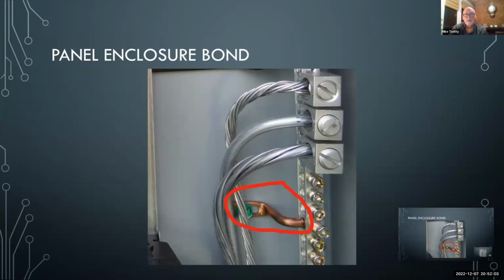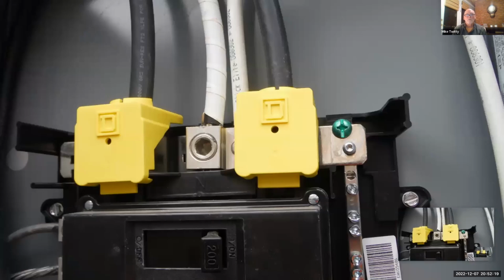That's probably aluminum, and that's probably a water pipe bond, that's solid one. So that's a listed main bonding jumper. This is probably an Eaton panel. That's kind of their style. This is a Square D, the green screw up at the right. That is the main bonding jumper in this panel. Different manufacturers have different methods of their listed bonding techniques. That screw is bonding the neutral bar there at the top that you're seeing, all the way through that plastic back plane, and it's screwed into the tapped hole in the metal can.